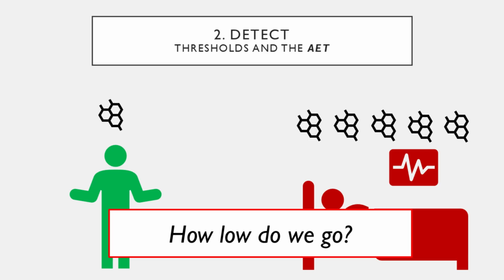So therefore, the FDA and other regulatory bodies need to look for some sort of minimum threshold of a detection capability in order to understand, are you even capable of detecting those potentially harmful amounts? It's very possible that any analytical method could say, hey, we looked for arsenic and we didn't find it. Is that because you just had a poor sensitivity in your instrument? Or is that because you had a great sensitivity and you can say with confidence that arsenic is not present at levels above a picogram per milliliter or something like that? So let's describe how some of these places describe these minimum thresholds.